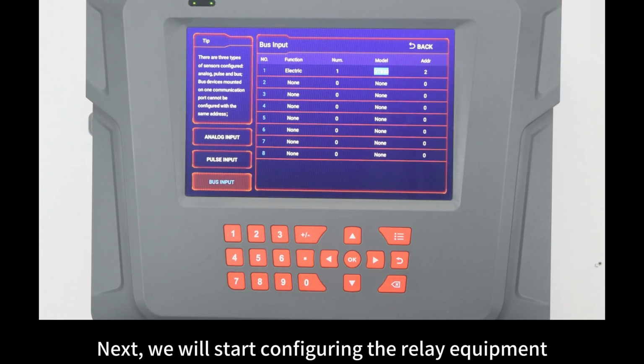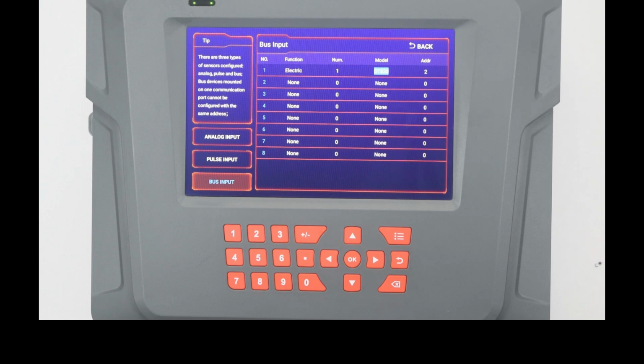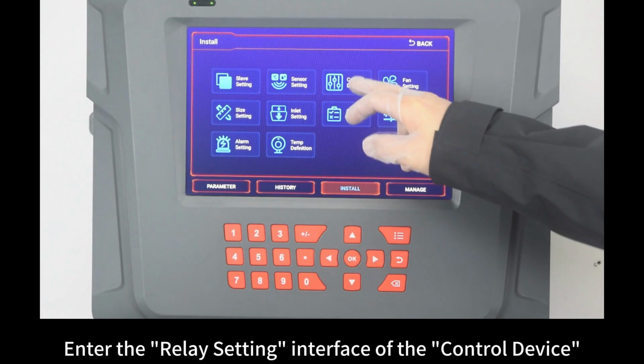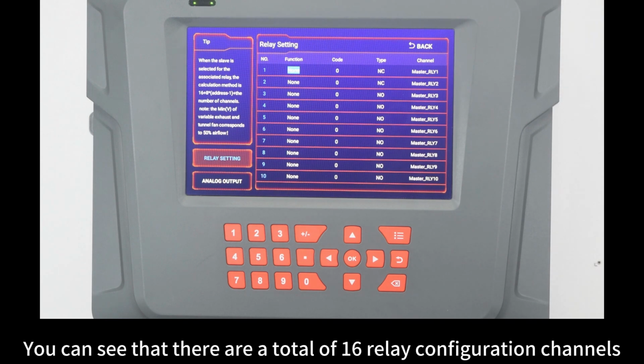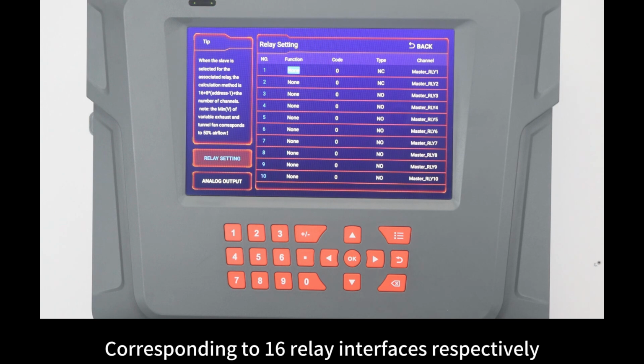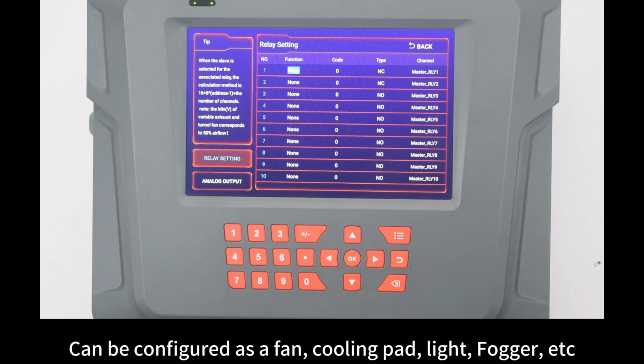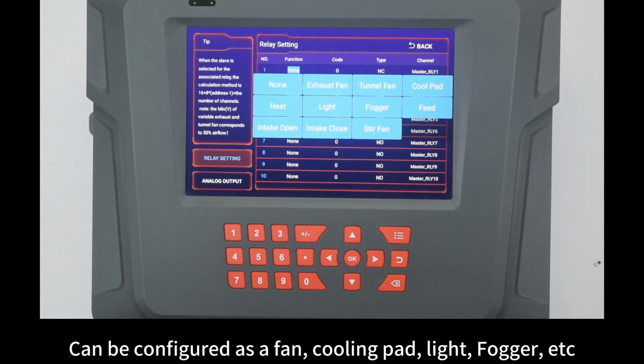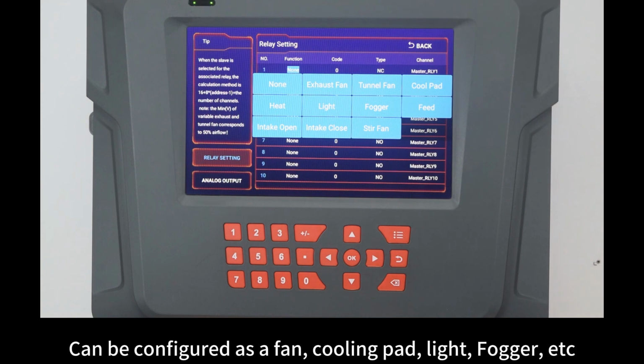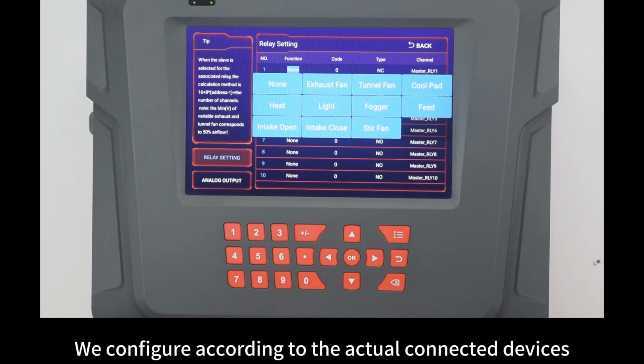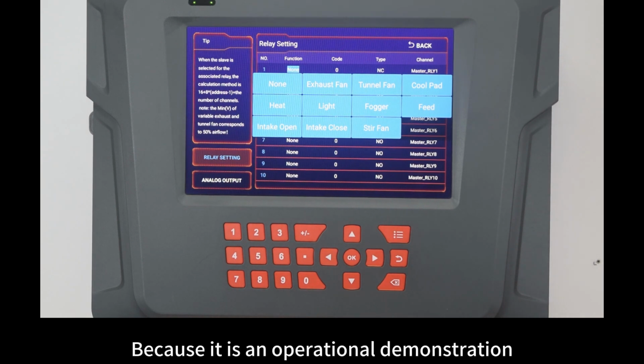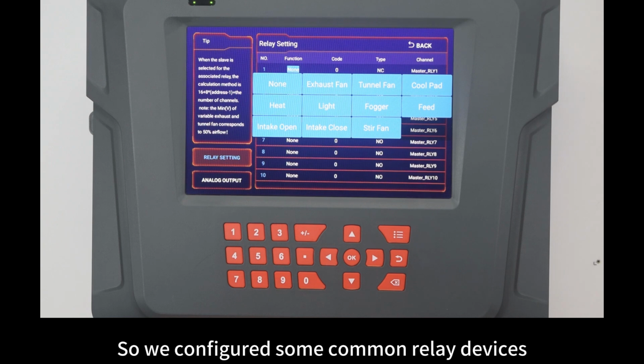Next, we will start configuring the relay equipment. Enter the relay setting interface of the control device. You can see that there are a total of 16 relay configuration channels, corresponding to 16 relay interfaces. They can be configured as a fan, cooling pad, light, fogger, etc. We configure according to the actual connected devices. Because it is an operational demonstration, we configured some common relay devices.